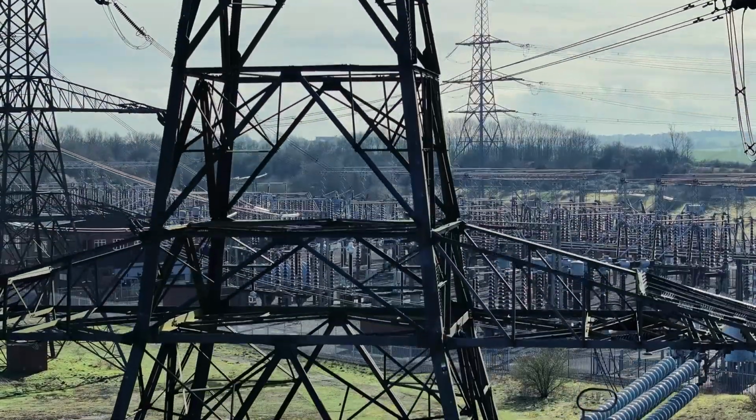So whilst I mentioned it can buy at 5 kilowatts and demand at 11 kilowatts, sometimes the national grid doesn't quite like that. We've effectively got 2 types of application. A G98 application, which limits your ability to export to 3.68 kilowatts. Now this export can also be limited under what's called a G99 application as well, or G100 if they change that. Most inverters do not have the ability to limit what they can export to the grid.